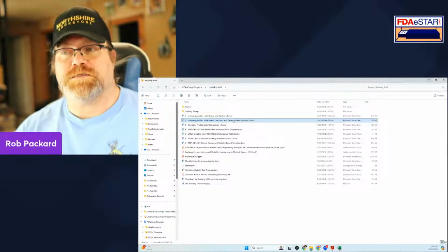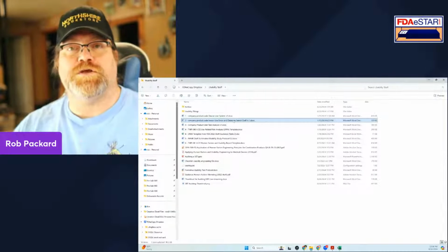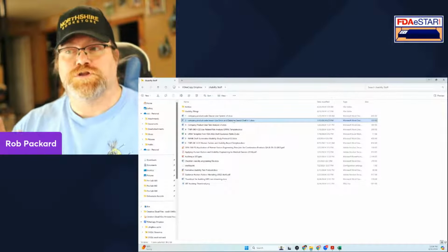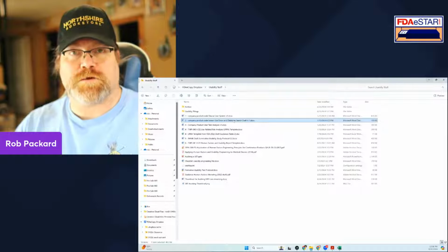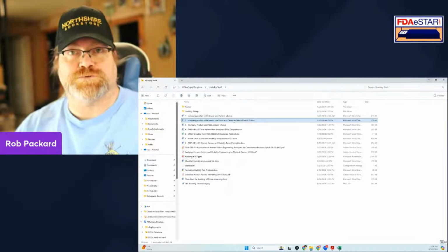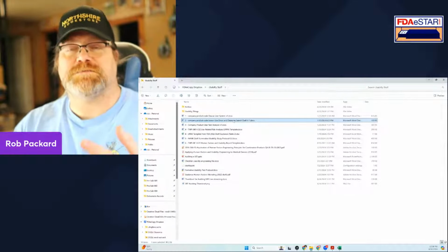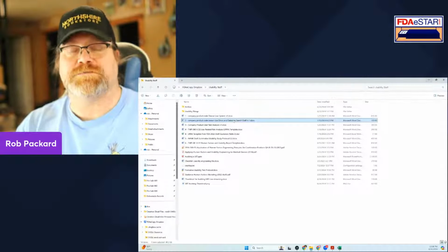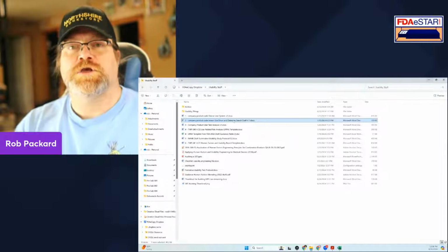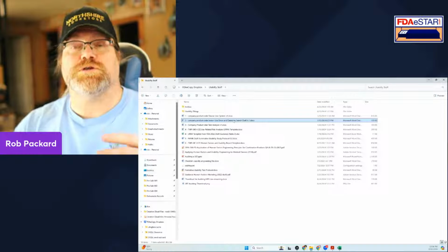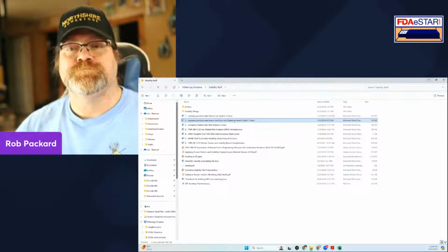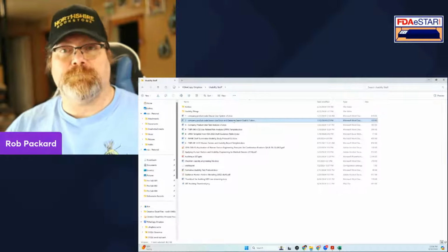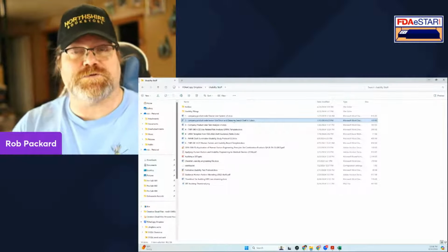They also are going to expect you to identify what the known use errors are out there. So we have a special document just for documenting known use errors that were found in a database search. So you'd look through the MAUDE database, you'd look through the TPLC database, you'd look at recalls, you'd look at other countries. You'd look at your own post-market data if you had any previous versions on the market.